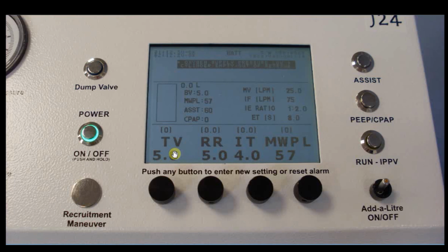And if we were to fill this system with gas now, we'd see the piston rise up here until it got to the midpoint, which is 10 litres. And at 10 litres it would stop moving up, because the virtual bag size is set at 10 by the combined value of the buffer volume and the tidal volume. If we set the buffer volume to 10, then the combined size would be 15, and this would rise up to the 15 litre point and stop up here and not get any bigger.